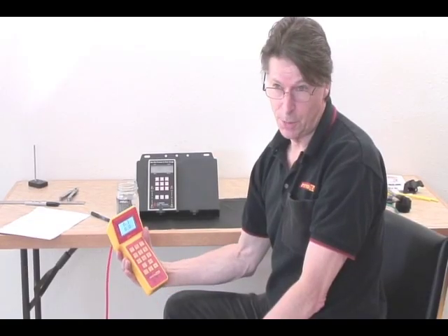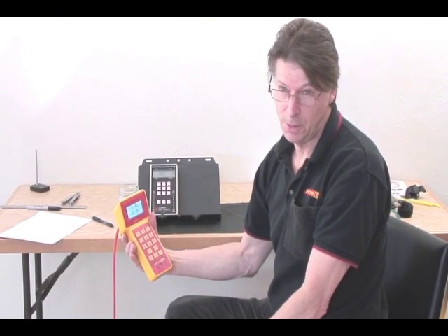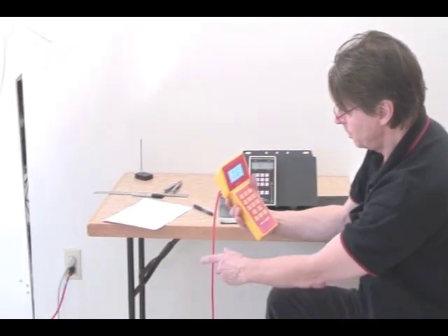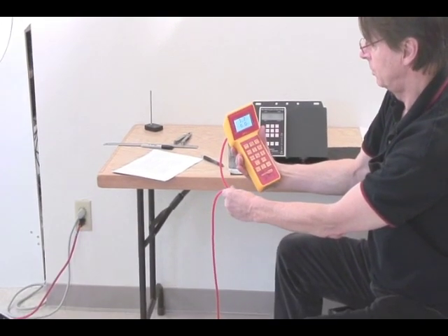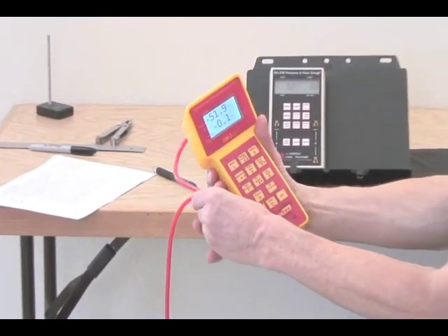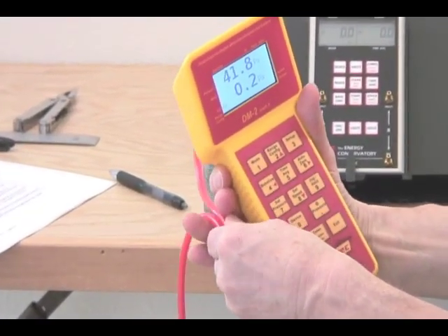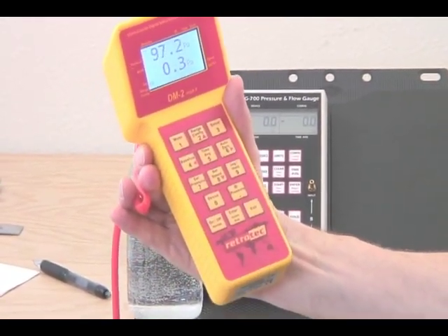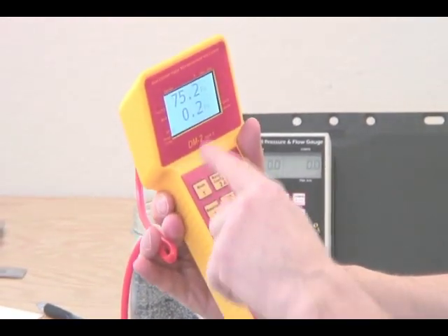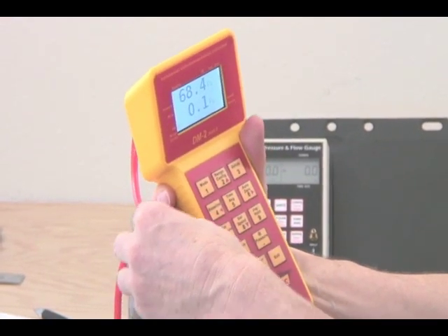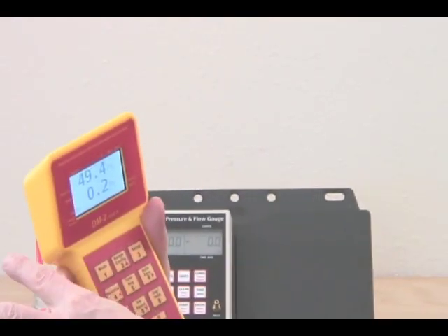So the next thing we're going to talk about is the old pinch tube problem. And I've seen people close tubes in doors and see the effects of a pinch tube. So if we were to pinch this tube right now, you notice that the pressure goes up, and it doesn't really matter what kind of pressure is applied on the end of the tube. It doesn't pay any attention to it. So if we blow in the end of this tube, it doesn't do anything. The pressure that the gauge is seeing is between here and the gauge, and the air has been compressed in this piece of tube, so it doesn't pay any attention to it.